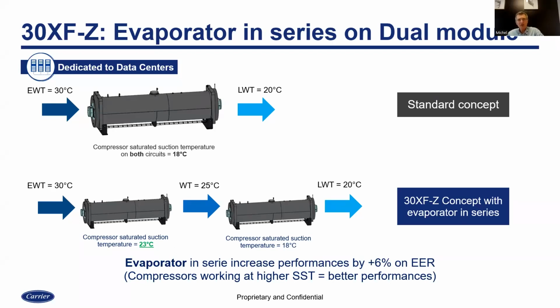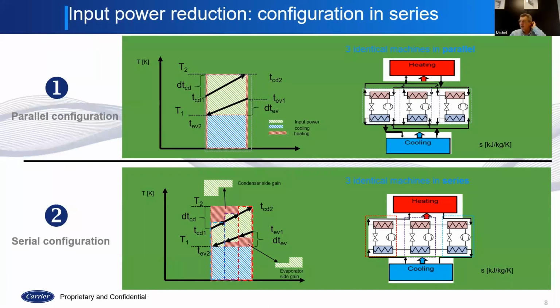Excuse me. It's very important not only for this specific chiller. This is something we developed in my previous life, mainly for district heating applications, and eventually the connection between data center and district heating. So I will try to do a little bit of thermodynamics here just for a second. I'm talking here about the generic case of units installed in series versus units installed in parallel from a water perspective. As an example, I'm talking about water-cooled systems, but it applies to air-cooled systems as well.